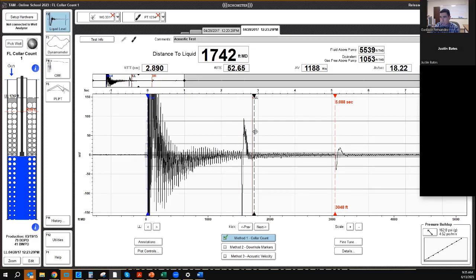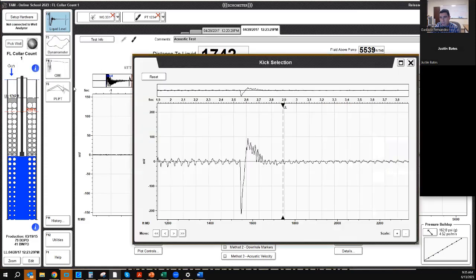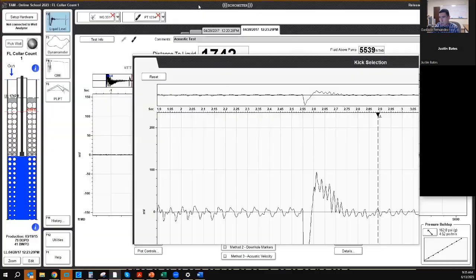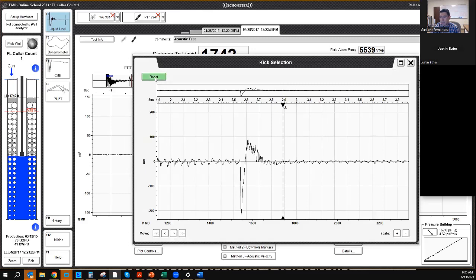Even if you're playing with that, you can always ask the software where it thinks the fluid level is, and it will do an automatic liquid level selection. I can go back there by going to fine tune and liquid level, make this full screen, and by clicking reset, the software will put the liquid level line where it thinks the liquid level is.